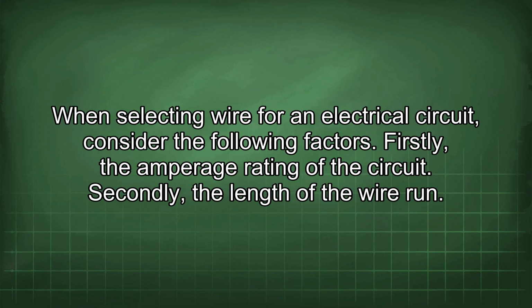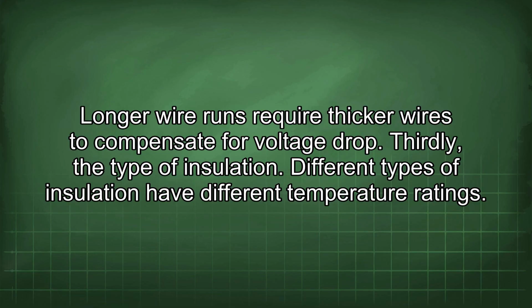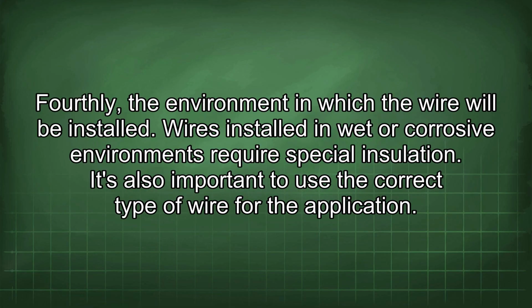When selecting wire for an electrical circuit, consider the following factors. Firstly, the amperage rating of the circuit. Secondly, the length of the wire run. Longer wire runs require thicker wires to compensate for voltage drop. Thirdly, the type of insulation. Different types of insulation have different temperature ratings. Fourthly, the environment in which the wire will be installed. Wires installed in wet or corrosive environments require special insulation.